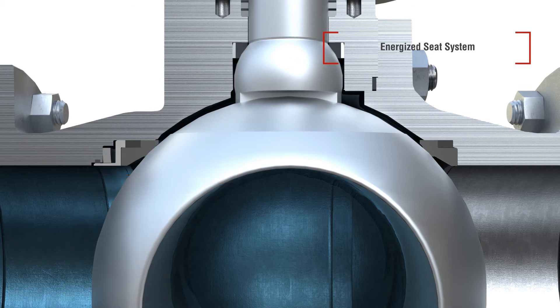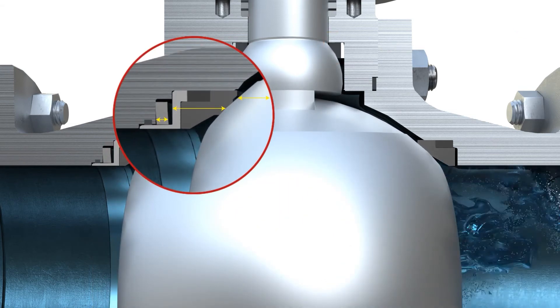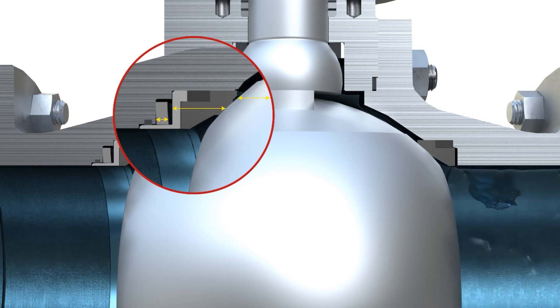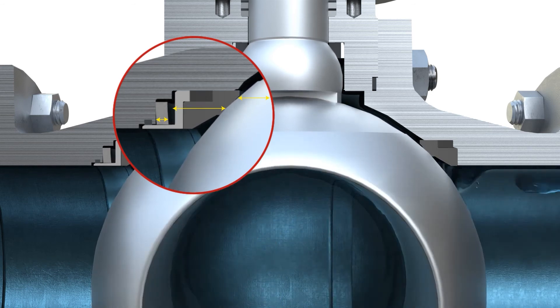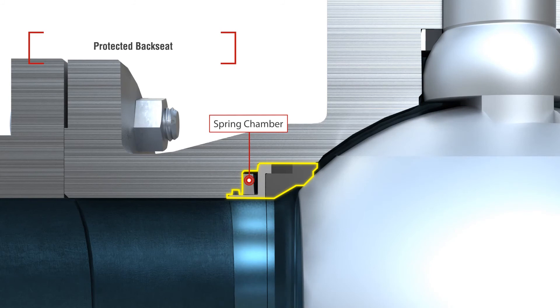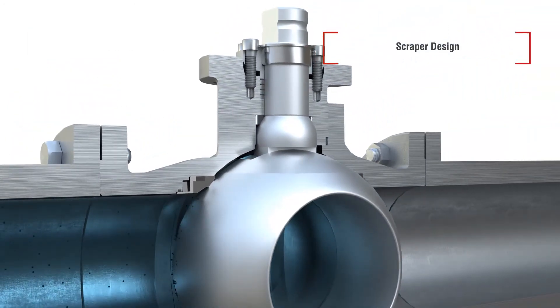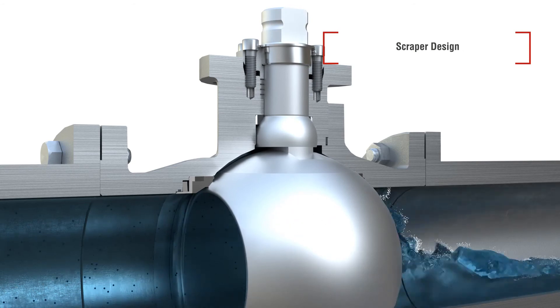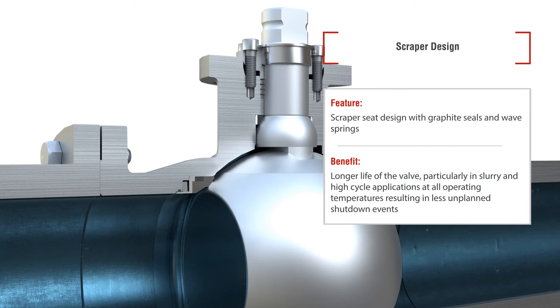These components acting in synchrony during valve operation at a wide range of pressure and temperature will protect the ball and seats from excessive wear by maintaining a consistent surface contact between them. For applications with a high content of solids, the high-temperature trim version, as well as all trunnion versions of Tough Seat Performance Series valves, are fitted with a wiper seal to further protect the back seat arrangement. In combination with the wiper seals, all Tough Seat Performance Series valves are designed with scraper seats as a standard feature to remove, with every operation of the valve, any solids deposited on the ball surface.